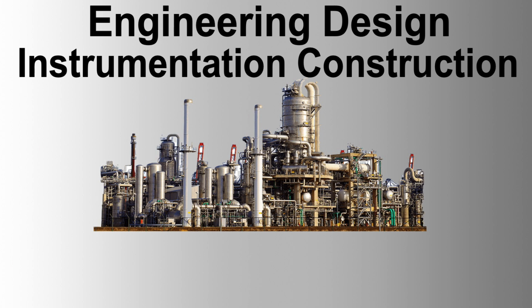Instrument and junction box termination. Cables shall be terminated in instrument and junction boxes as per the project drawings. Entry points shall be sealed to prevent the ingress of moisture and contaminants. Where specified, junction boxes shall be equipped with terminal strips to facilitate the connection of field instruments. Cable glands used for cable entry into junction boxes shall be of a type suitable for the cable and the environmental conditions.